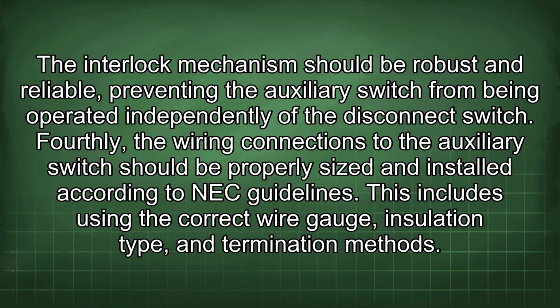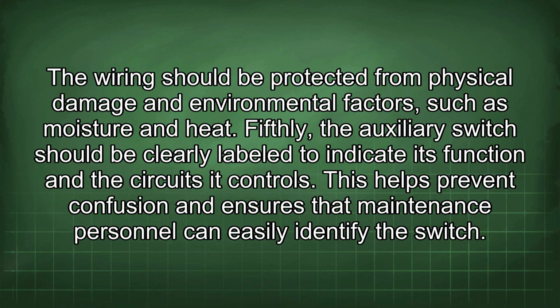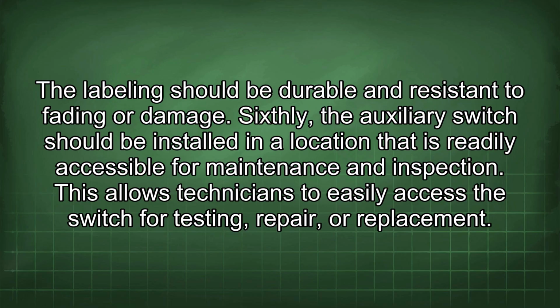Fourthly, the wiring connections to the auxiliary switch should be properly sized and installed according to NEC guidelines. This includes using the correct wire gauge, insulation type, and termination methods. The wiring should be protected from physical damage and environmental factors such as moisture and heat. Fifthly, the auxiliary switch should be clearly labeled to indicate its function and the circuits it controls. This helps prevent confusion and ensures that maintenance personnel can easily identify the switch. The labeling should be durable and resistant to fading or damage. Sixthly, the auxiliary switch should be installed in a location that is readily accessible for maintenance and inspection.